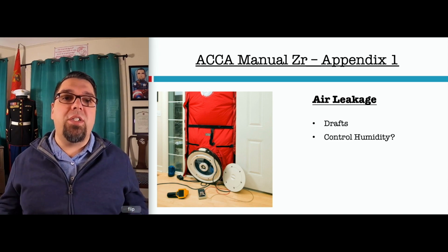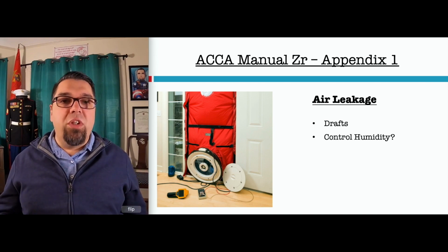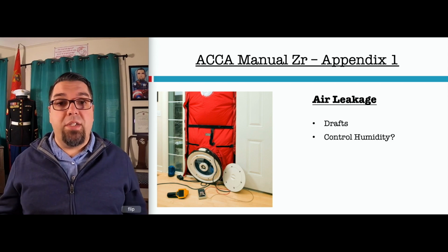Large leaks first, then worry about all the boots and all those other things. Pan bays are another one. Really, really hard to seal a pan bay. Probably just want to duct it. You shouldn't be installing pan bays these days anymore.